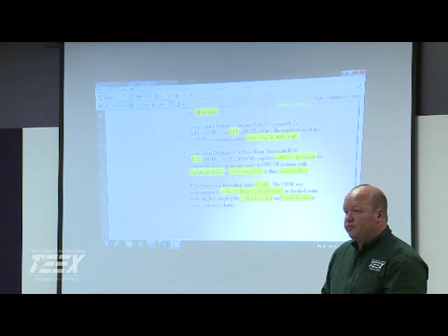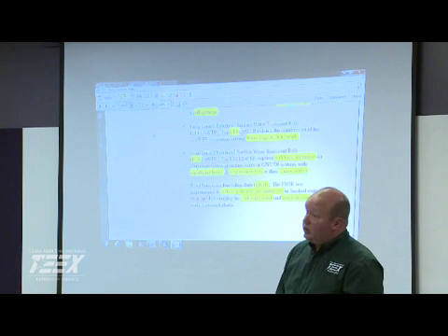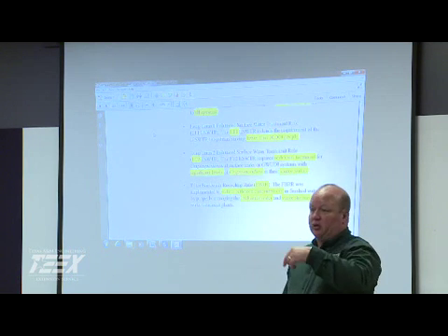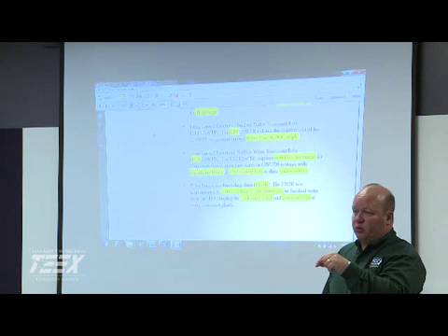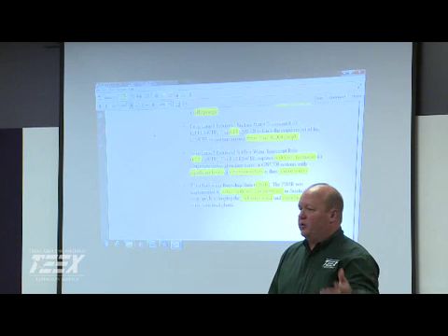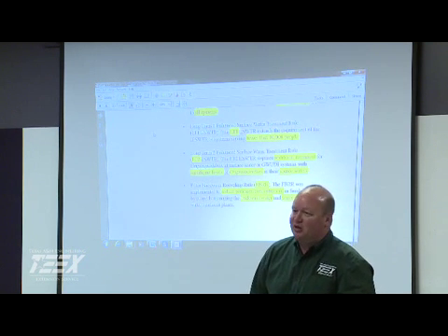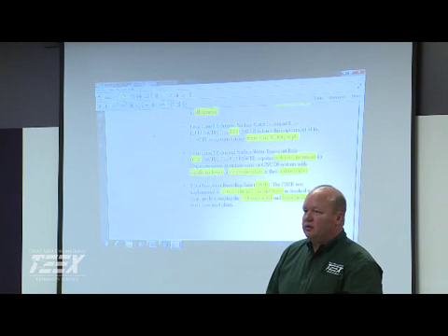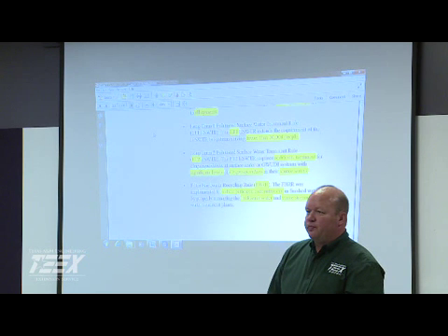They tell you what it can be, and his might not be the same as mine. That's based on the receiving stream. Ours is a running stream that runs out into like a slough, and that stream runs all the time. You think that it would dilute it more, but they don't take the volume into consideration. They look at the quality of the water in the river, and you can't degrade that quality. So if you happen to have a really clean river and he's got one that's a lower quality, the limits differ. Like I said, it was a 1 for years, and in the past couple of years I think it changed to a 0.04, so that was a big drop for us.